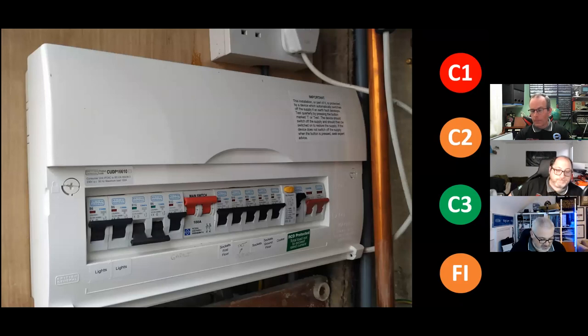When located beneath the gas service where it's caused condensation, in this case, 7671 only states precautions shall be taken. There is no mention of distances that gas and electrical services should be in 7671. However, minimum distances of segregation are given in table 6.2 of BS 6891:2015. And it says minimum segregation between gas and electrical intakes is 150 mil, and minimum segregation between gas service pipes and electrical accessories, switchgear or wiring is 25 mil. This is all guidance for them, not guidance for us. Is that right? Yes. This is guidance for the gas fitters and the plumbers.